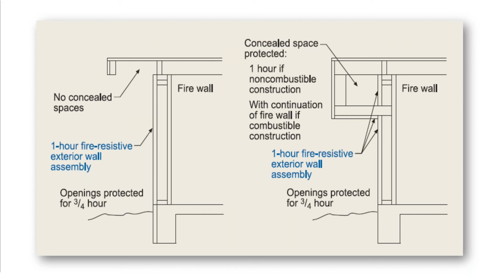And then the vertical continuity. You've got firewall, so we talked about horizontal. Now what happens at the top? Firewall shall extend from the foundation to a termination point at least 30 inches above both adjacent roofs. So you've got a firewall between the two buildings. It goes all the way up. Again, no horizontal offsets for the firewall, but then how does that wall terminate? All the way up and at least 30 inches above both adjacent roofs.